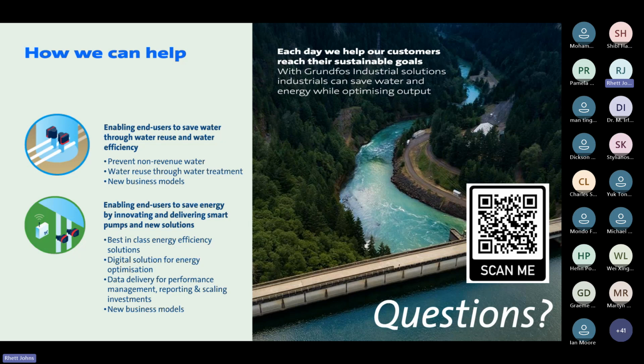So let's say your BMS knows that at a certain time of the day you need 3 bar worth of pressure, and then at night time you need 2.5 bar worth of pressure. If you pass that information down to your controller and change the control set point on the pump controllers, they'll just update their target and their running speed in order to match that new pressure. So as long as you've got a pressure sensor within the system, you pass down the required set point, it can then adjust the pressure set point that it's running those pumps to. So that should solve both of those issues if you go with a multi-pump system.